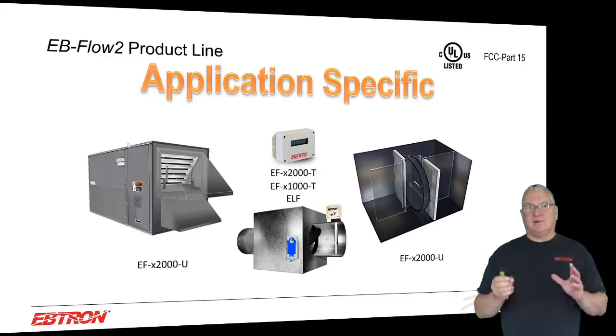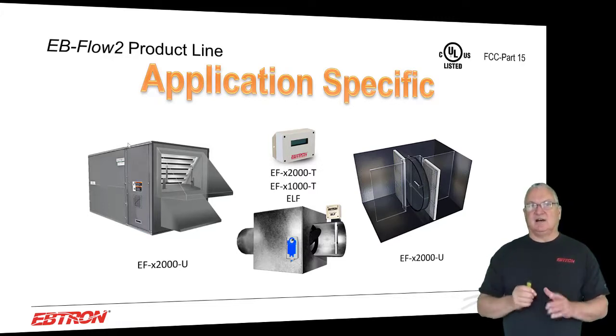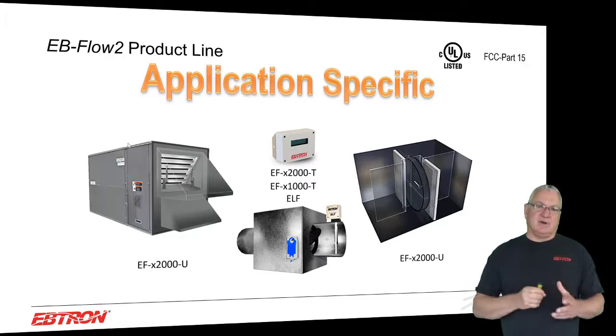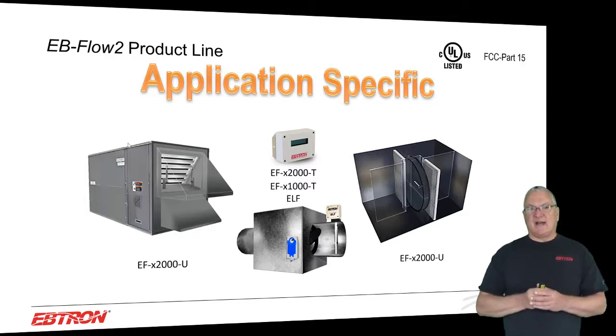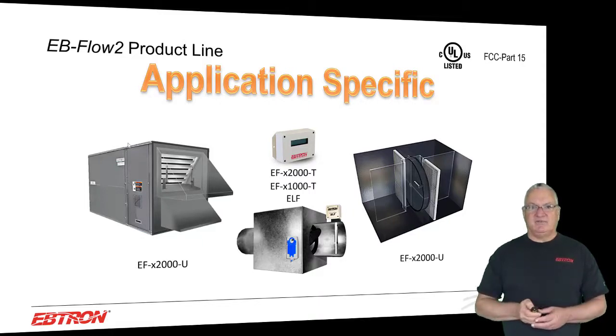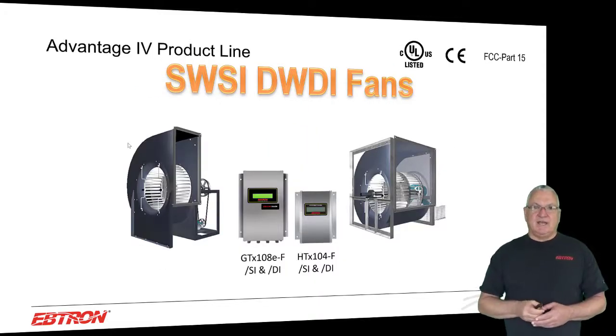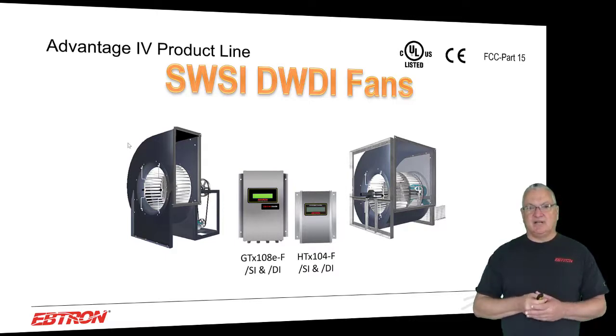When we get into the terminal box, we're talking about round ducts. It's 4 to 16-inch rounds is really the range it was designed for. So it's terminal box applications, it's your DOAS applications, it could be small tracking applications. In that model, it's either available with the remote transmitter like the U probes are, or with the electronics on the end of the probe, which is our EFX 1000-T, but most of you know it as the ELF if you've used it. When we get into fans, it's basically the same gold and hybrid transmitter options.